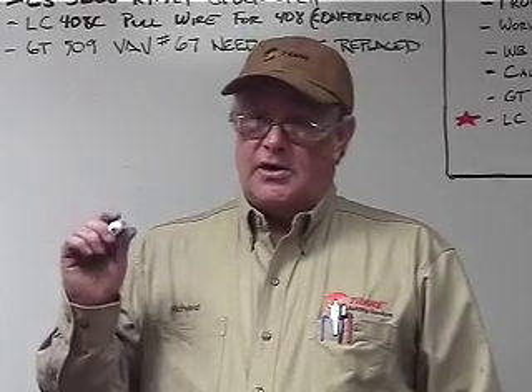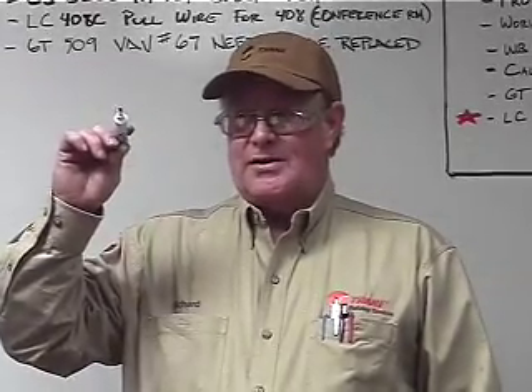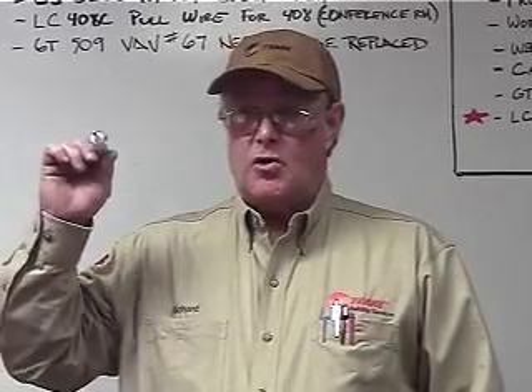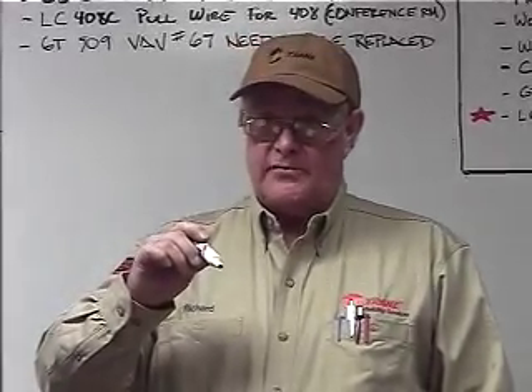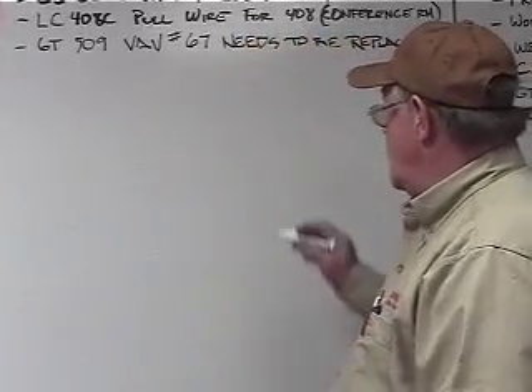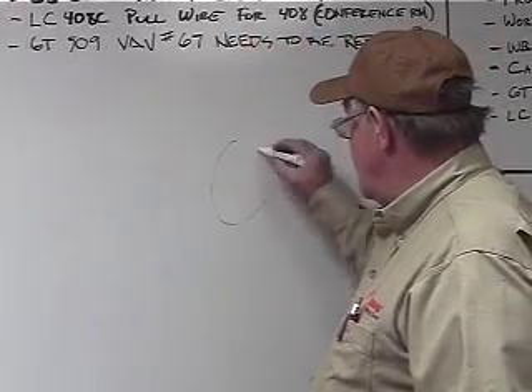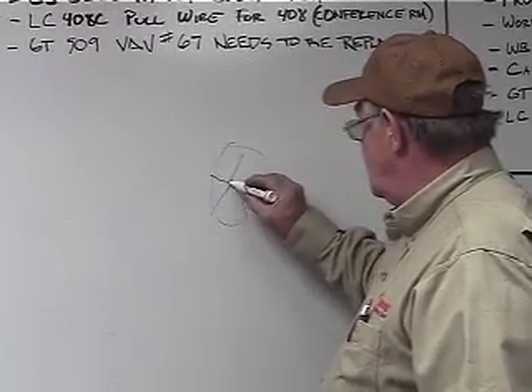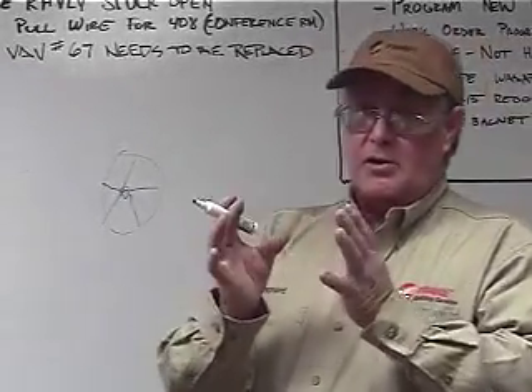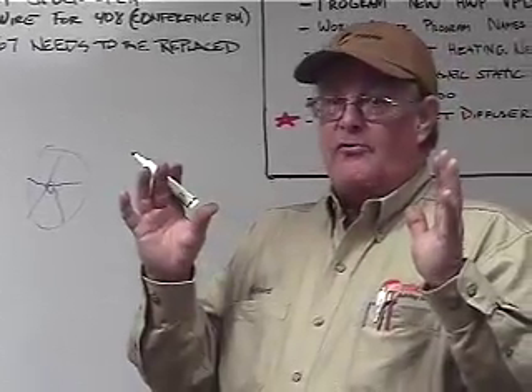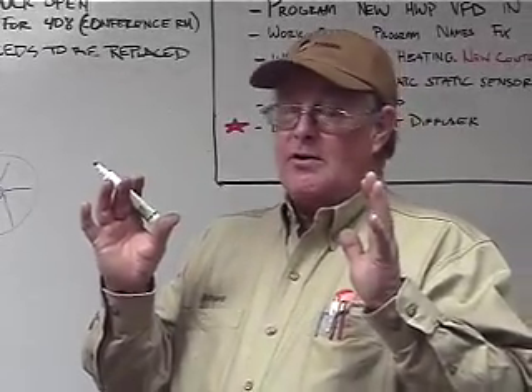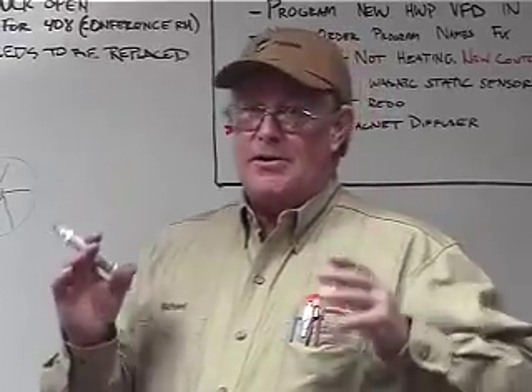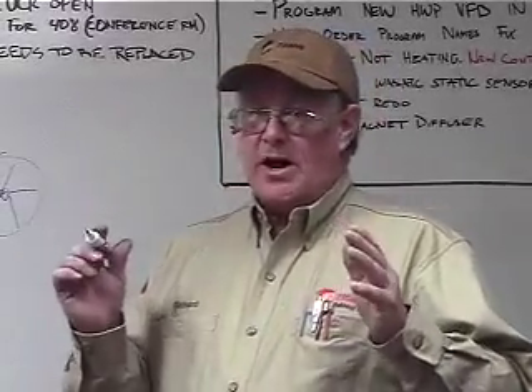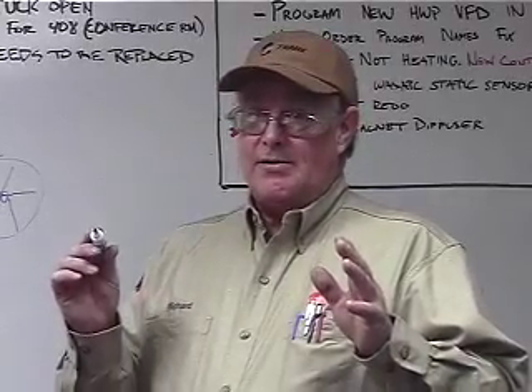A lot of times, let's say you've got 65-degree water going in and you're still trying to make 45-degree water, you've got those vanes that I was talking about that look pie-shaped. They open up. They modulate open and closed. They're going to open up fully, and when it opens up fully, your compressor starts working harder. So you're actually giving it more capacity.